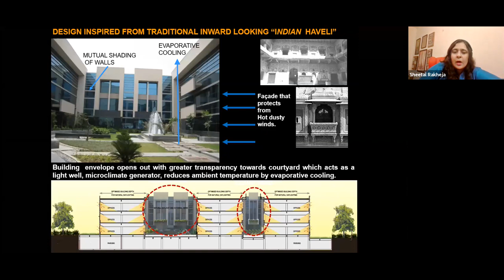These are some more images. Here, what we did was pre-cool the fresh air before it entered the building, and we were also running the complete system on full fresh air mode in fair weather seasons like November, October, February, March, when the outside temperature is much lower. But because inside you have lights on, heat from equipment, heat from people, you actually still need air conditioning.